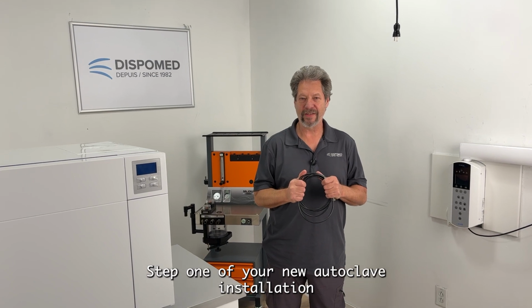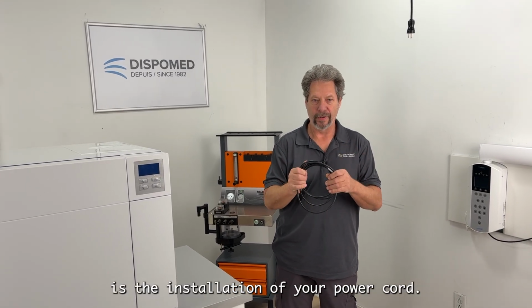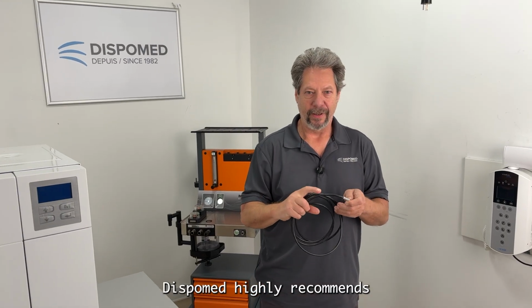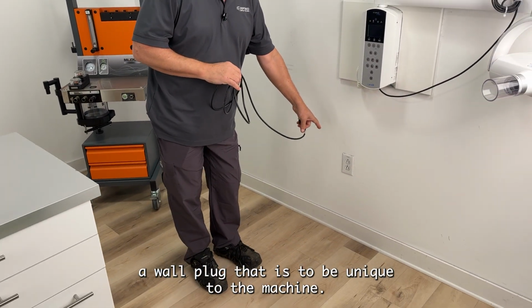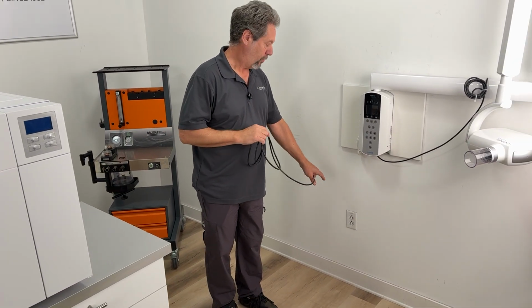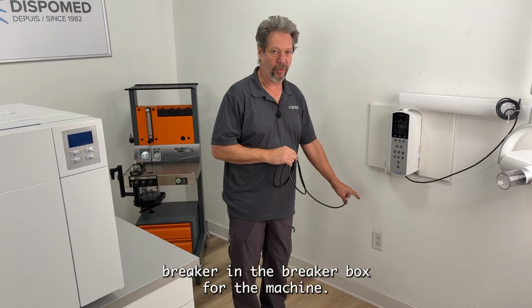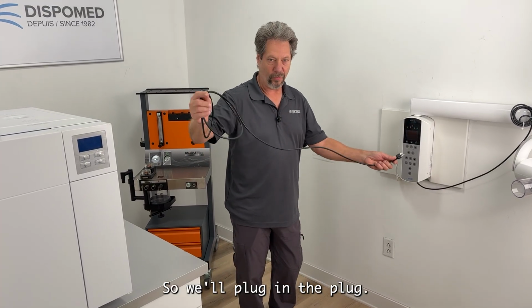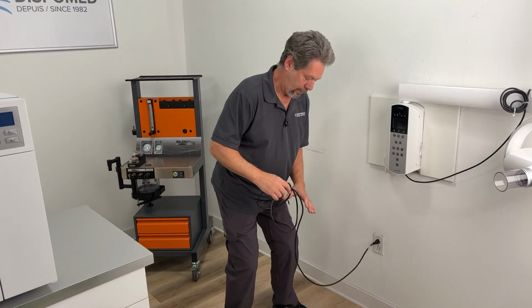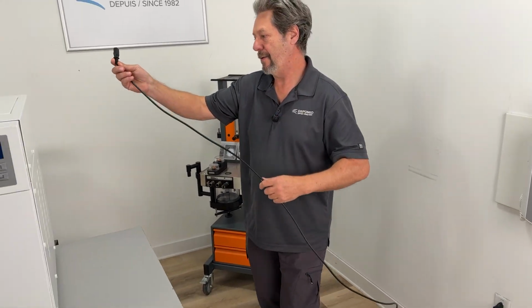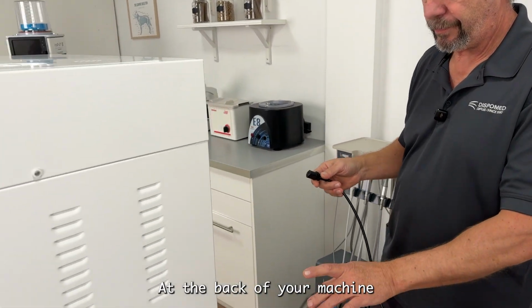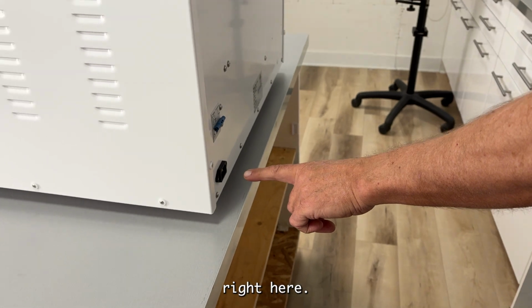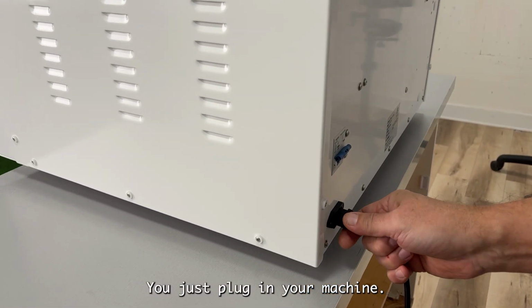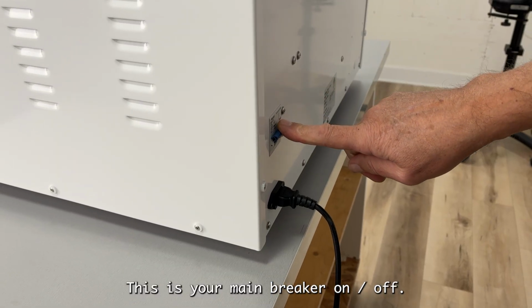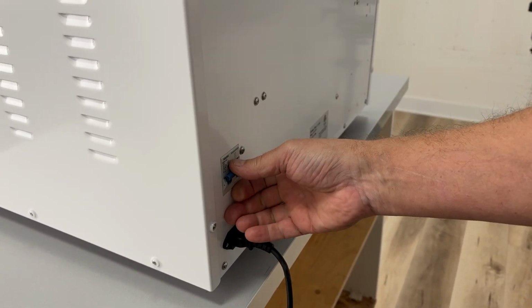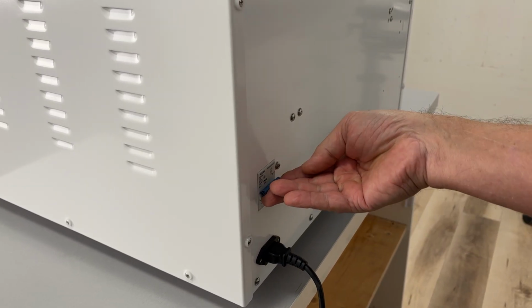Step one of your new autoclave installation is the installation of your power cord. Dispomed highly recommends that a wall plug is to be unique to the machine. What I mean by unique is to have its own breaker in the breaker box for the machine. So we'll plug in the plug, and at the back of your machine, right here, you just plug in your machine. This is your main breaker on off. So now this is in the off position, this is the on position.